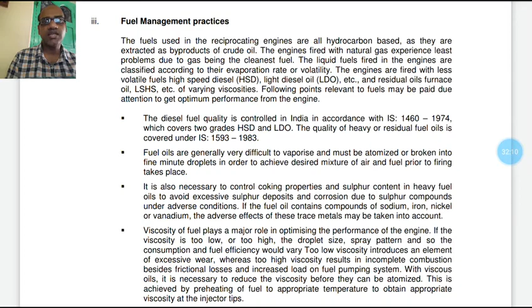Viscosity of fuel plays a major role in optimizing the performance of the engine. If the viscosity is too low or too high, the droplet size, spray pattern, and so the consumption and the fuel efficiency would vary. Too low viscosity introduces an element of excessive wear, whereas too high viscosity results in incomplete combustion besides frictional loss and increased load on the fuel pumping system. With viscous oil, it is necessary to reduce the viscosity before it can be atomized. This is achieved by preheating of fuel to an appropriate temperature to obtain appropriate viscosity at the injector tips.